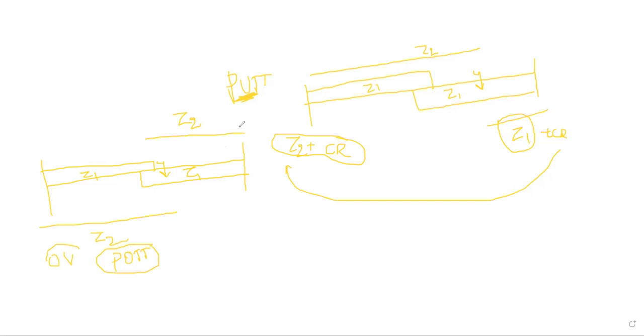That means the fault is there. See, breaker A is there, breaker B is there, and there is a fault at maybe below 80% of the line. No, we have to check both ends. If you see in this direction, it is also underreach only, right? Now let us just think about the PUTT. There is a fault at maybe 40%, or we can say 50%, of the line.